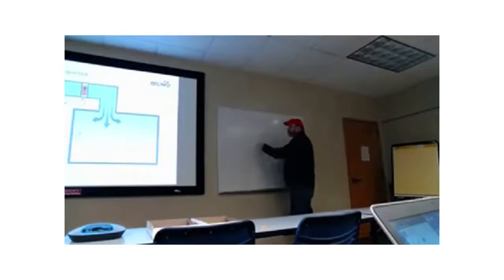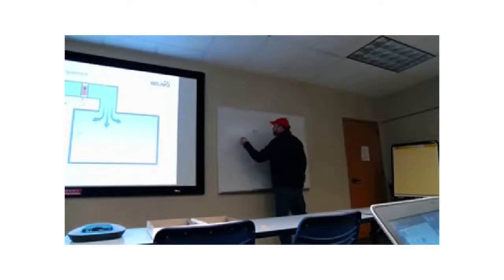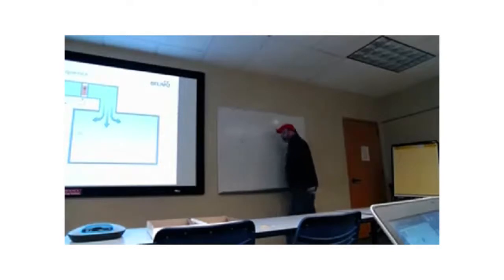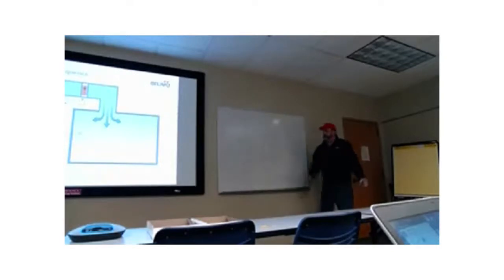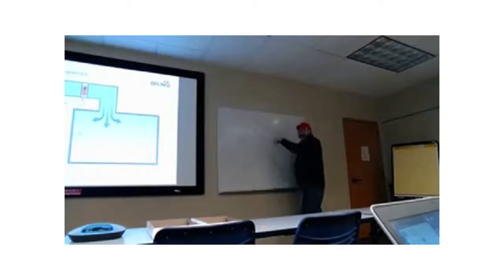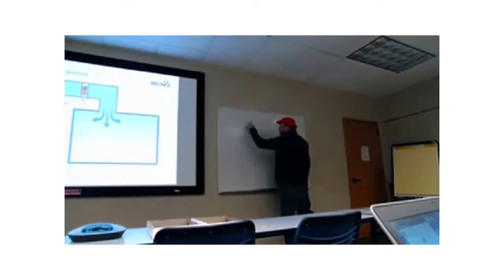It goes into the controller in a value that it can understand, right? It could be an analog signal, 4 to 20. It could be 2 to 10 volts, whatever it is. We call this, I don't know, you call it the process variable. It's known by a number of different names. So what's the other input to the controller? What it's supposed to be. Right, the set point. So the set point comes from everything.